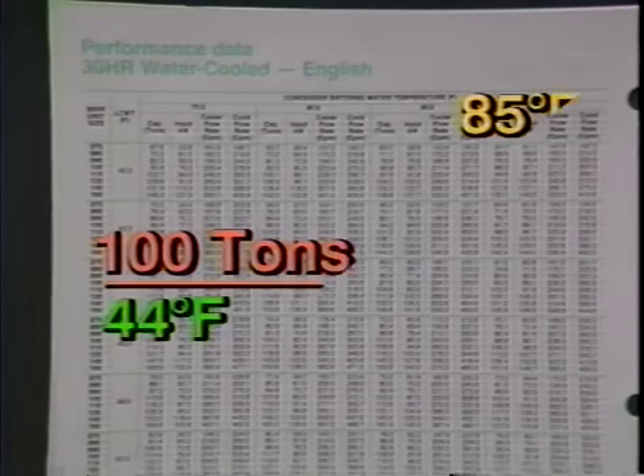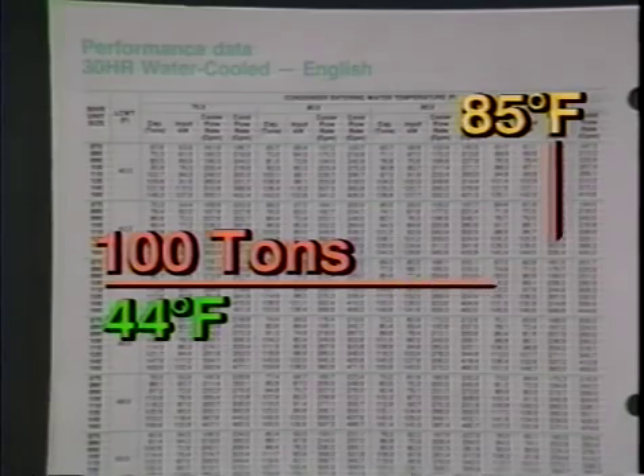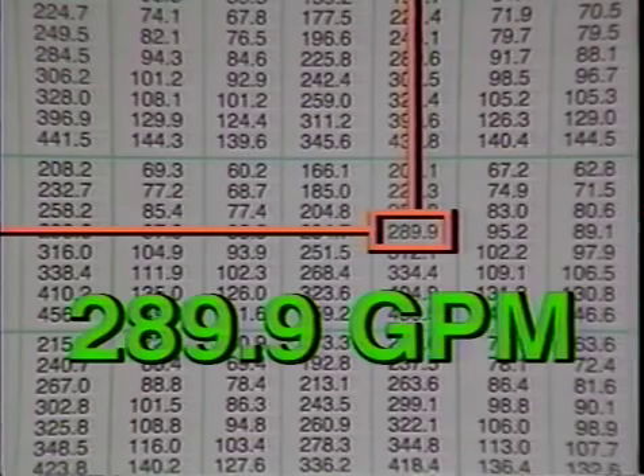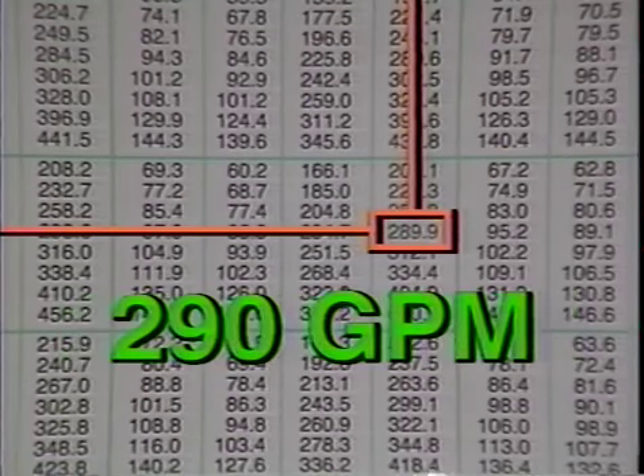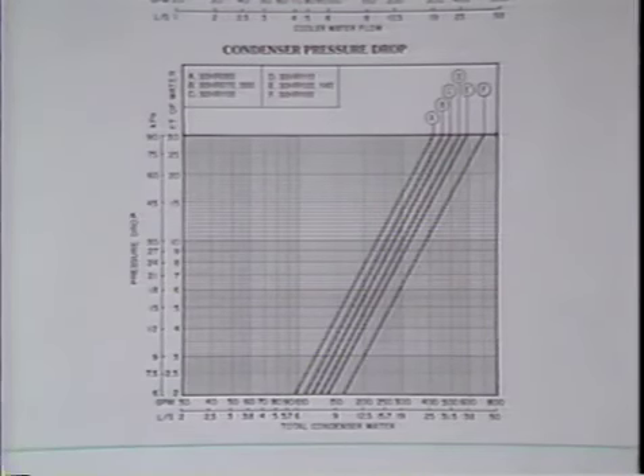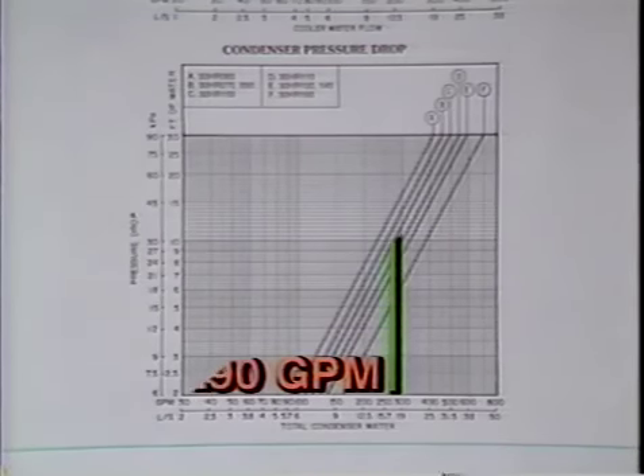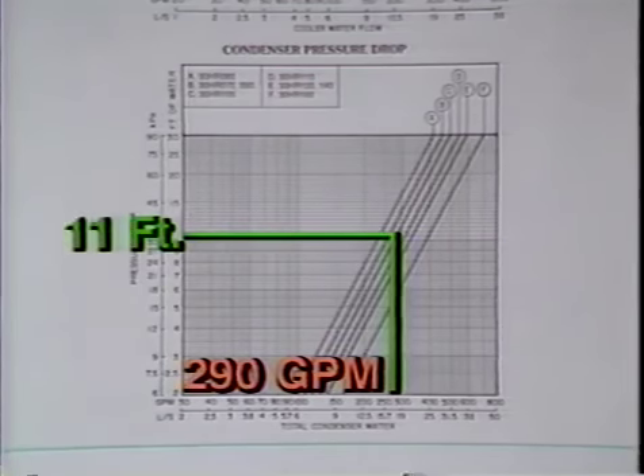To find the design GPM flow rate for this chiller, use the performance data chart in the manufacturer's application data. Starting with the 100-ton chiller with 44 degree Fahrenheit leaving chilled water and reading across to an 85 degree Fahrenheit condenser entering water, we find the design condenser flow rate to be 289.9 or 290 GPM. Now, look at the condenser pressure drop charts again. Start with 290 GPM and read up to the 100-ton chiller, then over to the pressure drop column where we find a design pressure drop of 11 feet.